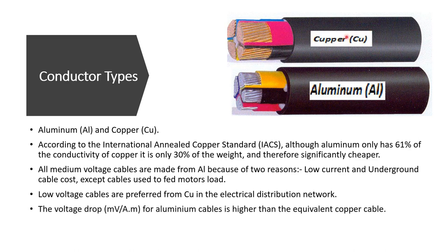The voltage drop for aluminum cables is higher than for copper because aluminum has lower conductivity, higher resistivity, and higher resistance. Voltage drop in cables is measured in millivolts per ampere per meter. To find the total voltage drop in a cable, multiply this value by the rated current absorbed by the load and by the cable length.